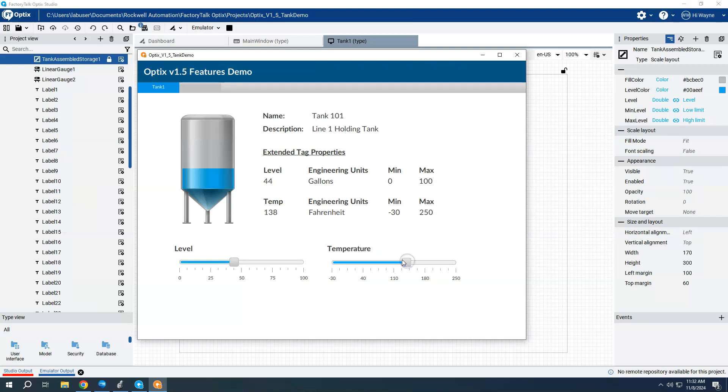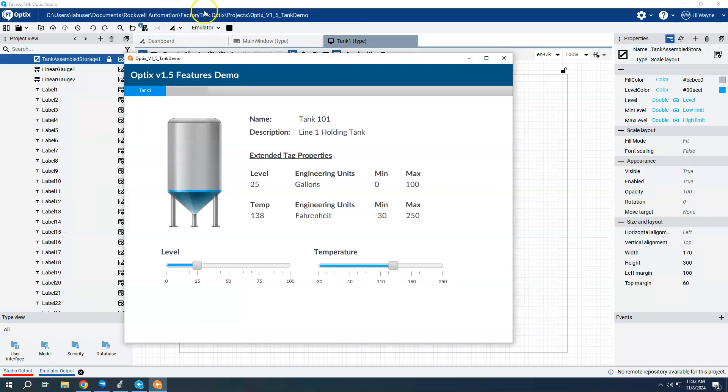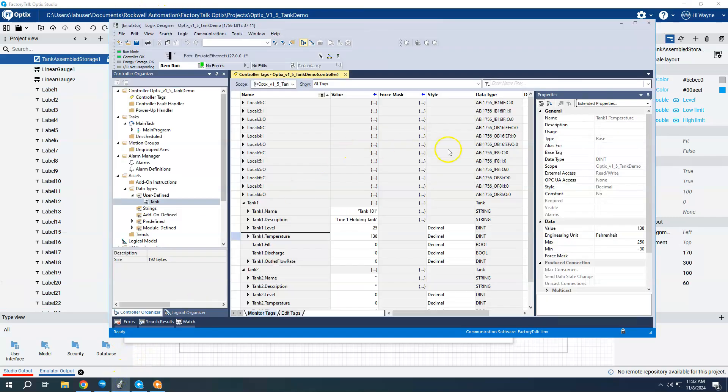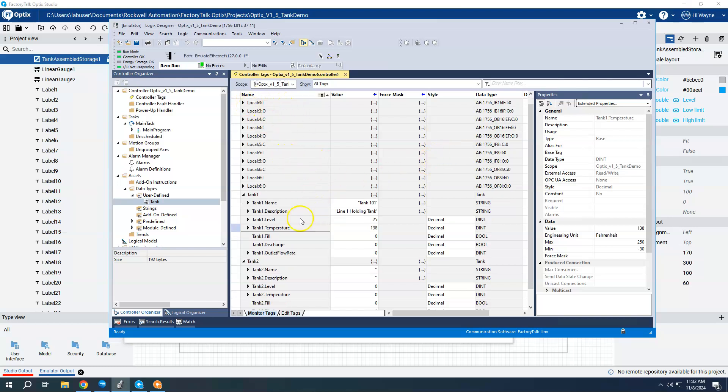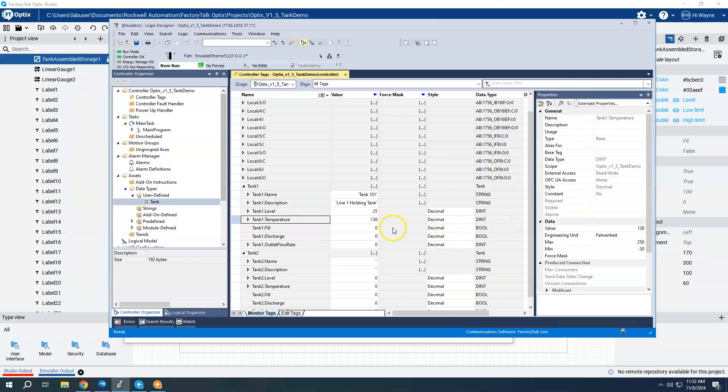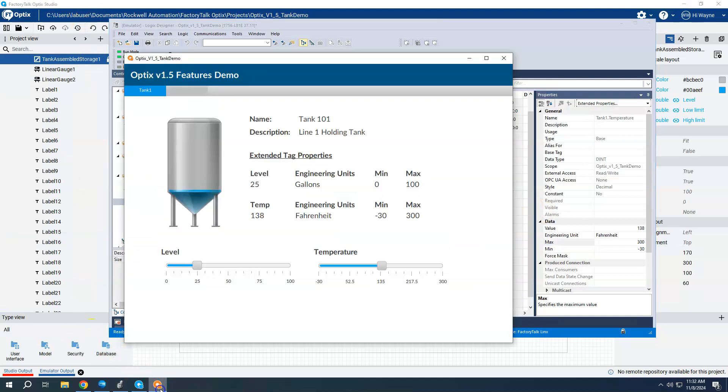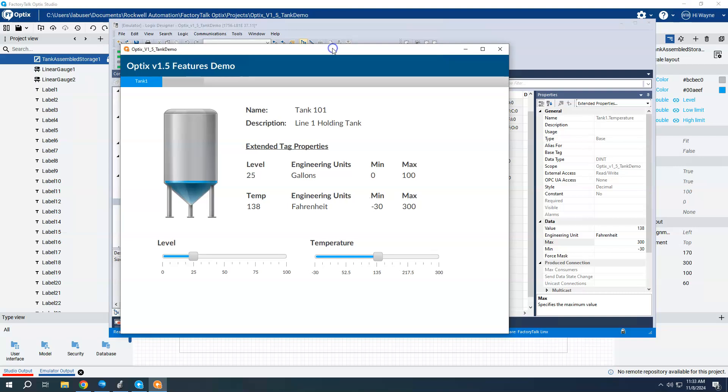So if I scroll up on here, we see that the number changes. Scroll down a level, we see the level changes. So pretty straightforward. If I were to attempt to come back here to my tag properties and change something, then I would be able to see that change on the Optix screen. So maybe let's see if I can do this live. Maybe we'll say we change our range to 300 now. And if I come back to the runtime, we can already see that the maximum setting did actually update to 300 as well as on my linear gauge here, changed the upper limit to 300 as well. So that's pretty nice and pretty interesting.